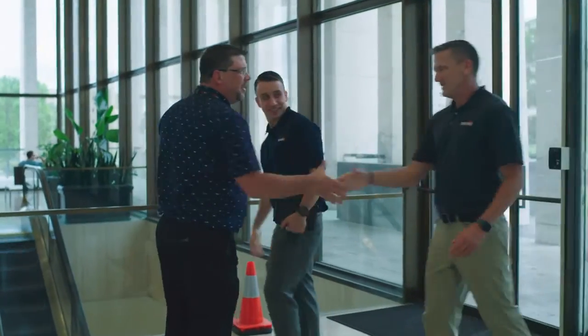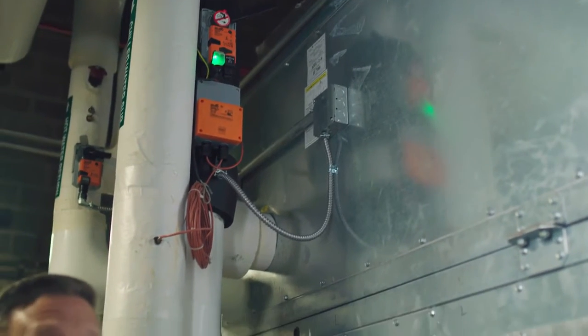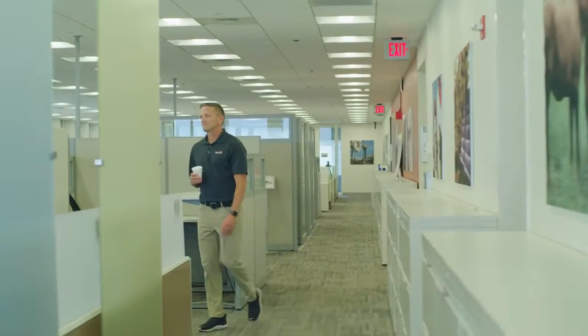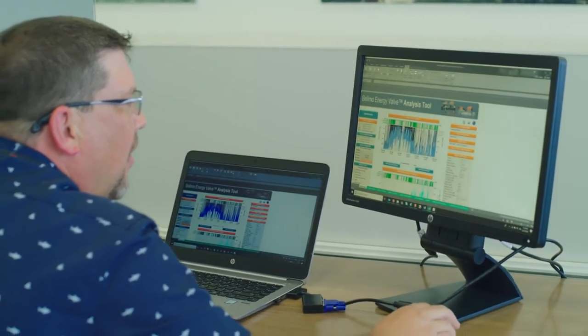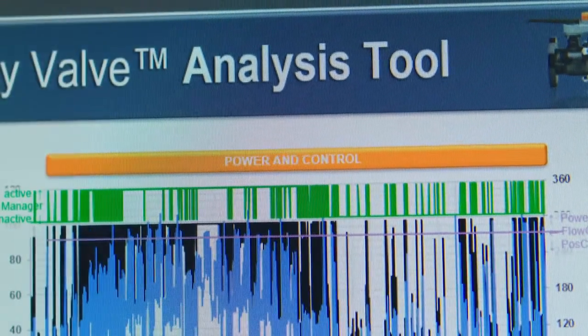The proof of concept was a major success — it exceeded my expectations. We went on in 2015 and did the full building, retrofitting all of the old inefficient valves and replacing them with brand new Belimo energy valves, which allowed us to solve the low delta T syndrome for the entire building and reduce overall energy costs. In the course of that project, we saved 49% in chilled water pumping — about $23,000 a year in total chilled water, pumping, and steam reduction savings. It paid back in about 2.4 years. It made my boss look good, it made me look good, it made our entire team and JLL look good within the state, and she even nominated me for awards within the company.